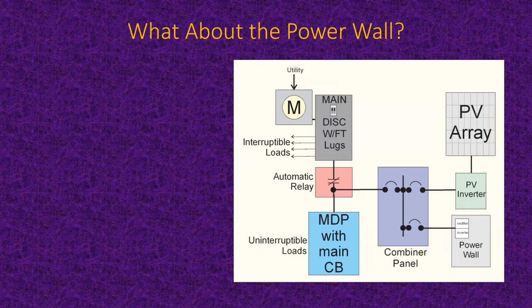Your combiner panel there is important because that's where you bring your PV down, and that PV is now turned into AC by the PV inverter, which could be microinverters. Okay. And so therefore we have an AC coupled system here now. So that means we have to have those same control constraints that we had in that last system. But not nearly as many boxes here, because that automatic relay is kind of in its own box in the combiner panel, but you can have additional circuit breakers in there in addition. So it's conceivable your main distribution panel would simply be run out of the combiner.